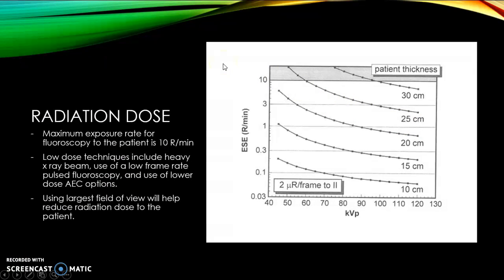Here is a chart of patient thickness and kVp radiation. The maximum exposure rate for fluoroscopy to the patient is 10R per minute. Low dose techniques include heavy x-ray beam filtration, use of a low frame rate pulsed fluoroscopy, and use of the low dose AEC options. Using a larger field will also help reduce patient dose.